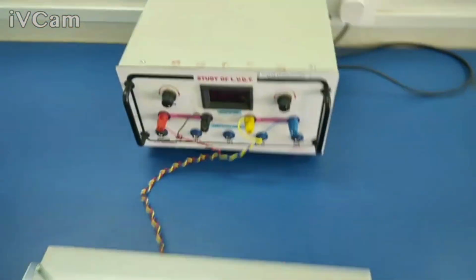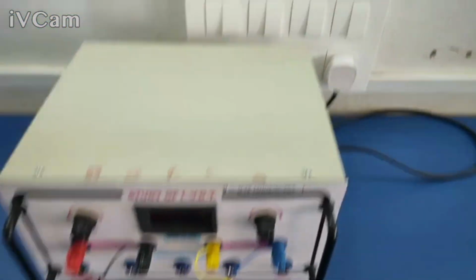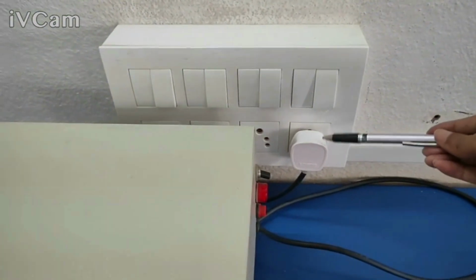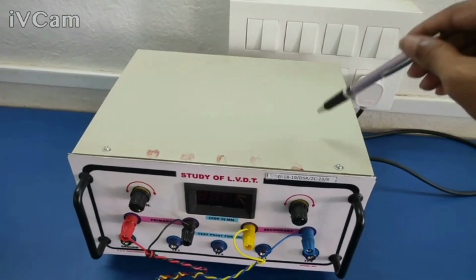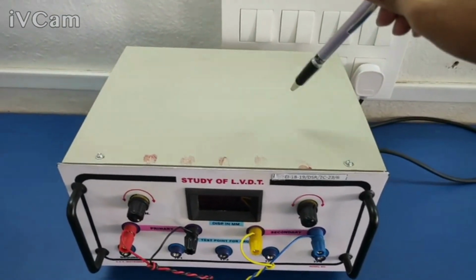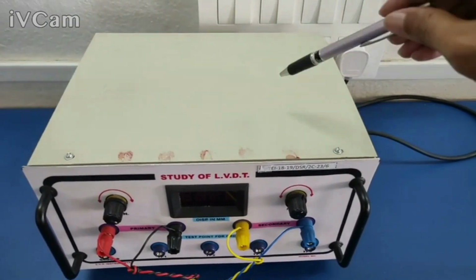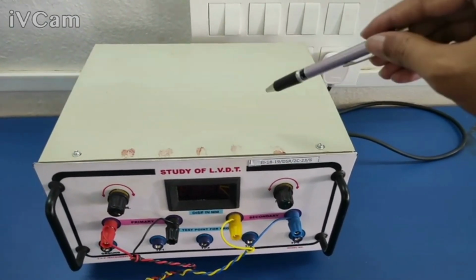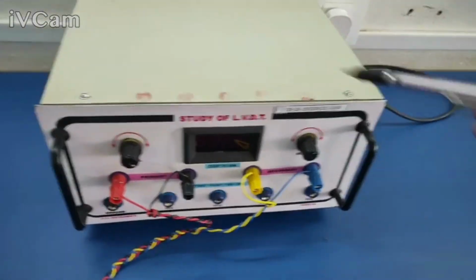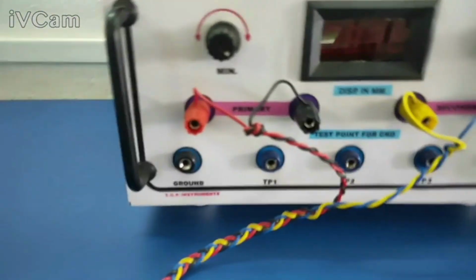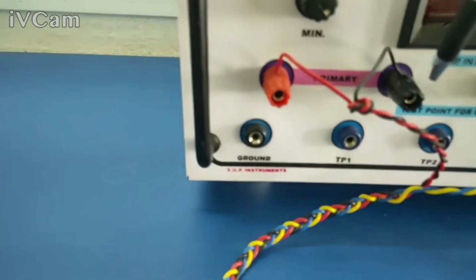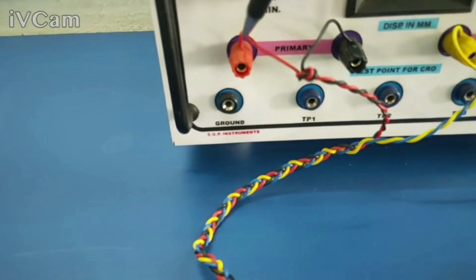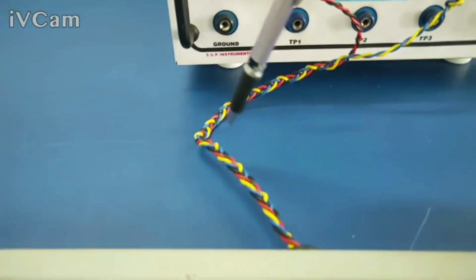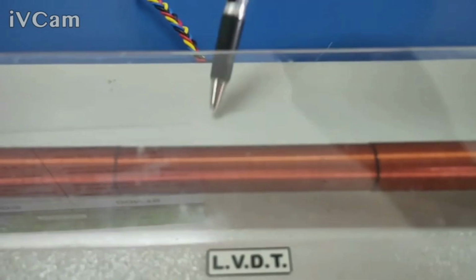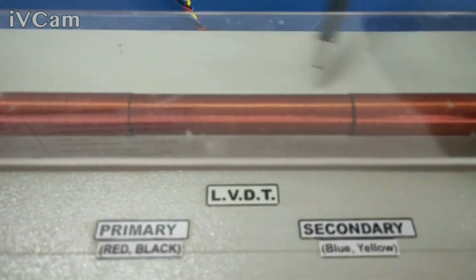Now what we have is a digital panel meter, as said. From the socket, a single-phase 230 volts AC supply is provided to the digital panel meter. Inside this we have used a step-down transformer which decreases the 230 volts AC to 5 volts AC. That 5 volts AC is available at the two points marked as primary winding. From here, with the help of a red wire and a black wire, we have given the 5 volts AC supply to the central portion, that is the primary winding, of the LVDT kit.